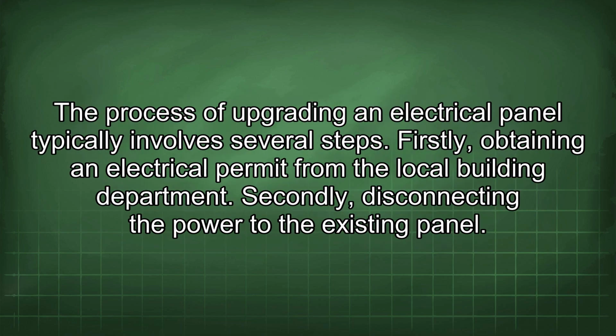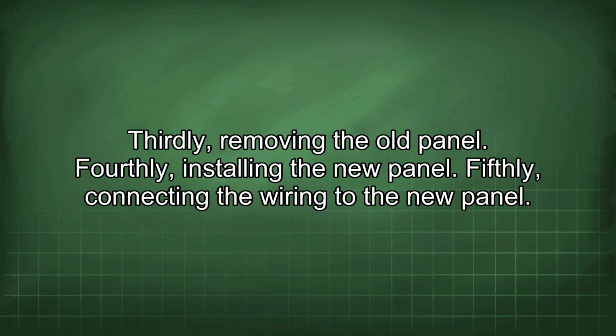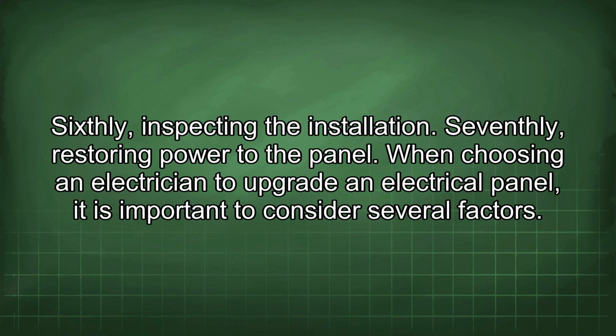The process of upgrading an electrical panel typically involves several steps. Firstly, obtaining an electrical permit from the local building department. Secondly, disconnecting the power to the existing panel. Thirdly, removing the old panel. Fourthly, installing the new panel. Fifthly, connecting the wiring to the new panel. Sixthly, inspecting the installation. Seventhly, restoring power to the panel.